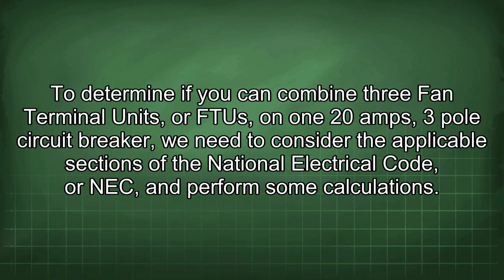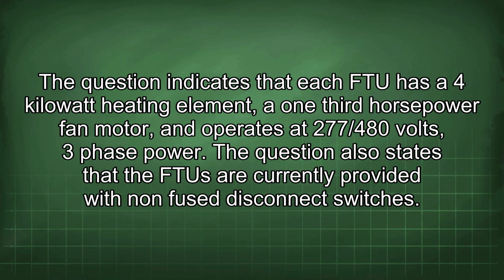To determine if you can combine 3 fan terminal units, or FTUs, on a 20 amp, 3-pole circuit breaker, we need to consider the applicable sections of the National Electrical Code, or NEC, and perform some calculations. The question indicates that each FTU has a 4 kilowatt heating element and a 1/3 horsepower fan motor, and operates at 277/480 volts, 3-phase power. The question also states that the FTUs are currently provided with non-fused disconnect switches.